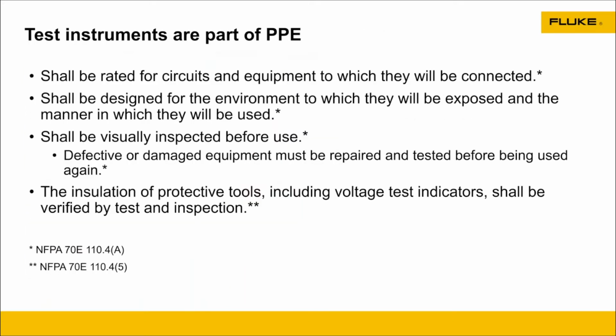So not only did we talk about clothing and knowing the correct PPE to have on, but part of NFPA 70E says that your test instrument is PPE. So having the right equipment to be able to work in that, knowing that your test leads and your meter qualify as that PPE, they should be visually inspected. They need to work correctly. You need to validate that it's working properly before you go in and touch those.